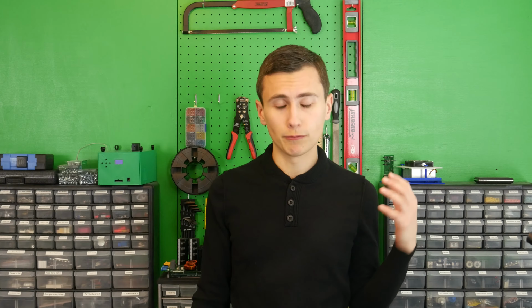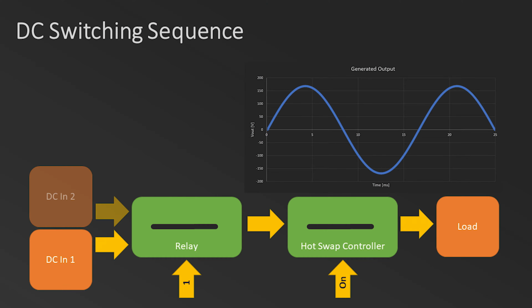That's why we added the hot swap controller to our design. This will handle the electrical switching so there's no arcing in the relay ever. This gives the relays approximately the rated mechanical switching life, which can easily reach 1,000,000 cycles for a given relay. Now that's quite an improvement, a couple thousand to 1,000,000. So let's walk through the sequence of events that we need to do in order for us to take the full benefit of this circuit and never switch the relay electrically.